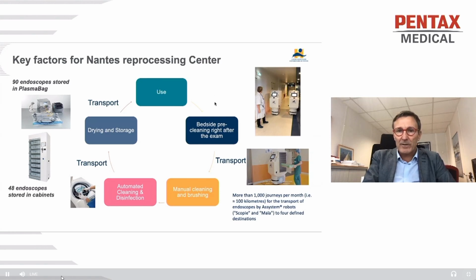The bedside pre-cleaning right after the exam, then the transport, and you can see here in these 2 photographs the two robots that we call Scopy and Mala. They perform more than 1,000 journeys per month, approximately 100 kilometers for the transports. Then the manual cleaning and brushing, then the automated cleaning and disinfection in a reprocessor, and then a transport to store endoscopes. So you can guess that we are only able to store 48 endoscopes in our 6 cabinets because we have only 8 places for each cabinet.